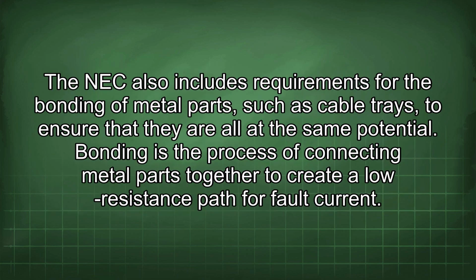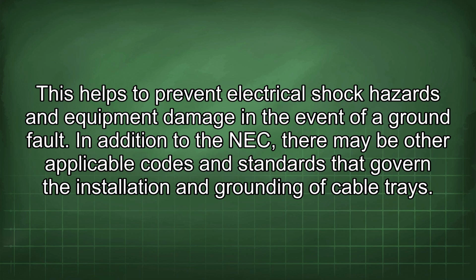The NEC also includes requirements for the bonding of metal parts, such as cable trays, to ensure that they are all at the same potential. Bonding is the process of connecting metal parts together to create a low resistance path for fault current. This helps to prevent electrical shock hazards and equipment damage in the event of a ground fault.